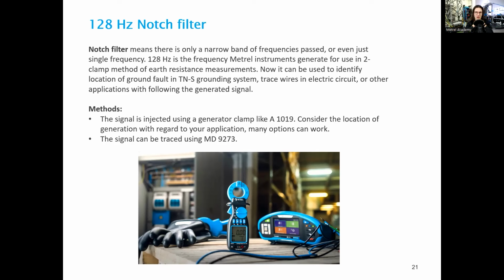for the two-clamp method of earth resistance measurement. And this frequency was selected because it is relatively far away from any supply frequencies or from their harmonics, so it can be easily discerned how it travels around the system. Now, generating signals into the ground system can have multiple uses. As I mentioned earlier, our testers use it in the two-clamp method to measure the resistance of the grounding system. However, the signal travels throughout the whole system, and now that we have a remote clamp, we can use this combination of generator and clamp to look at the problems in other places in the system.